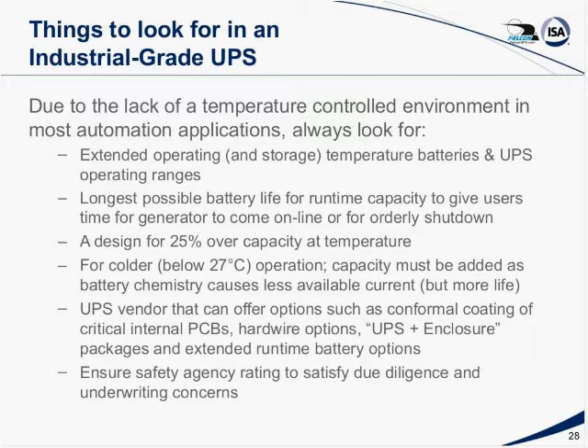And some UPS vendors offer options that may be very necessary in your environment, such as conformal coating, which takes away moisture and fungus from affecting the printed circuit components. They also have different hardwire options. They also sell the UPS with enclosure packages, and they have extended battery options such as battery packs and so forth. And above all, you should ensure that there's a safety agency rating for the temperature ranges you are operating over in order to satisfy your due diligence and underwriting concerns.